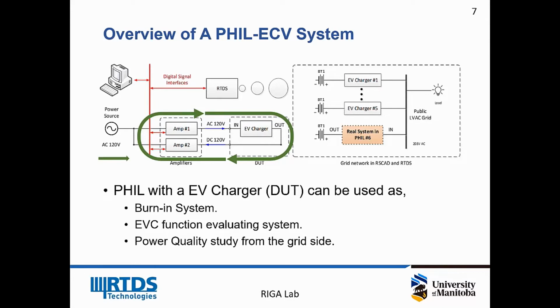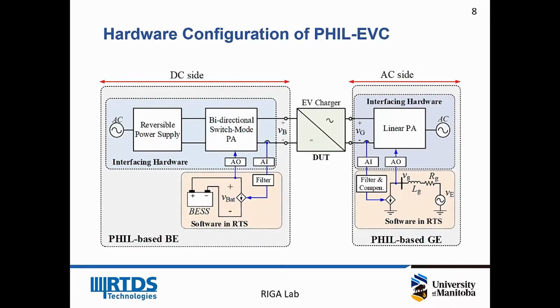Such a system is good for burn-in testing of EV chargers since the power is circulating in the loop. It only sources a little power from the real power source for compensating the loss in the whole system. It also can test the function of the EV charger, for example, protection. On the grid side, power quality can be studied with a simulated grid network. Then the DC side, that means the battery side.